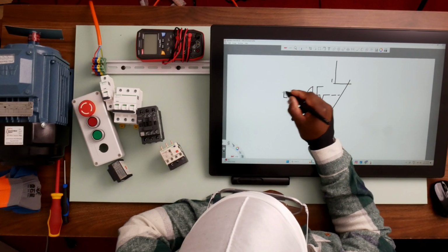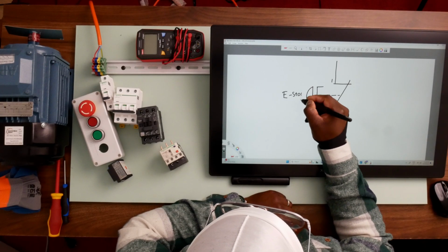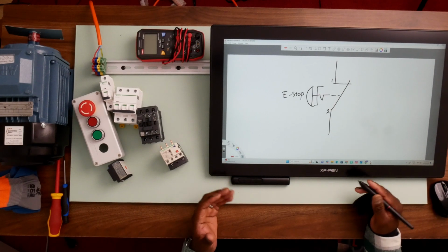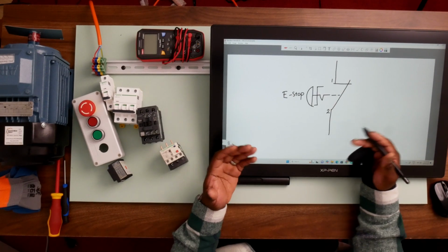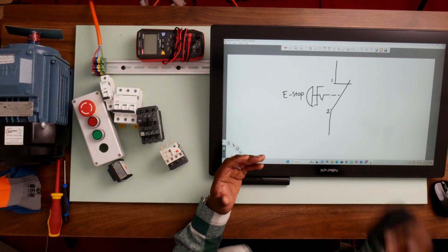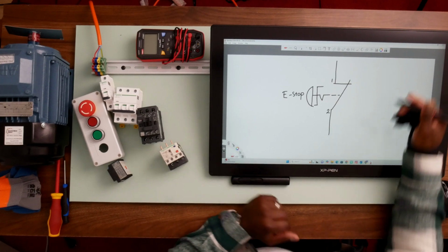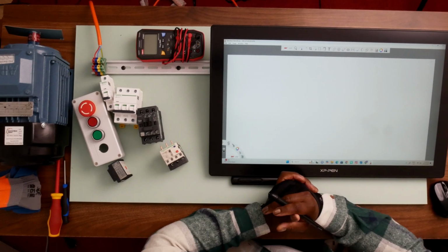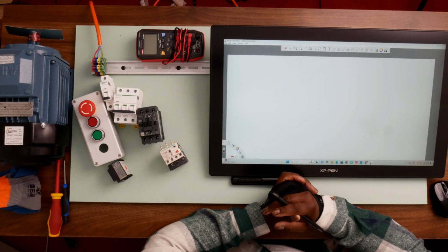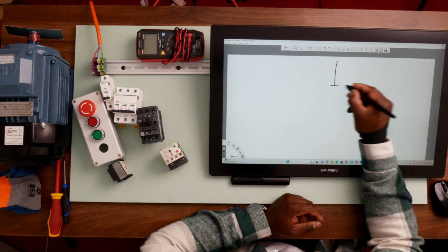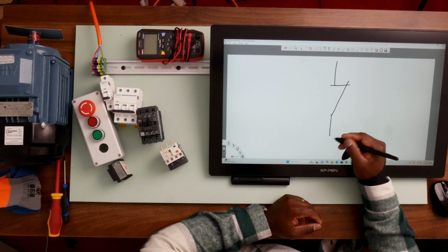So this is our e-stop. It's a normally closed contact. So this is the symbol that we're going to be using when we're drawing our schematics. The next in line is the stop push button. And just like the emergency stop button, for a simple direct online starter, we rely on the normally closed contact. We draw a normally closed contact like this one.